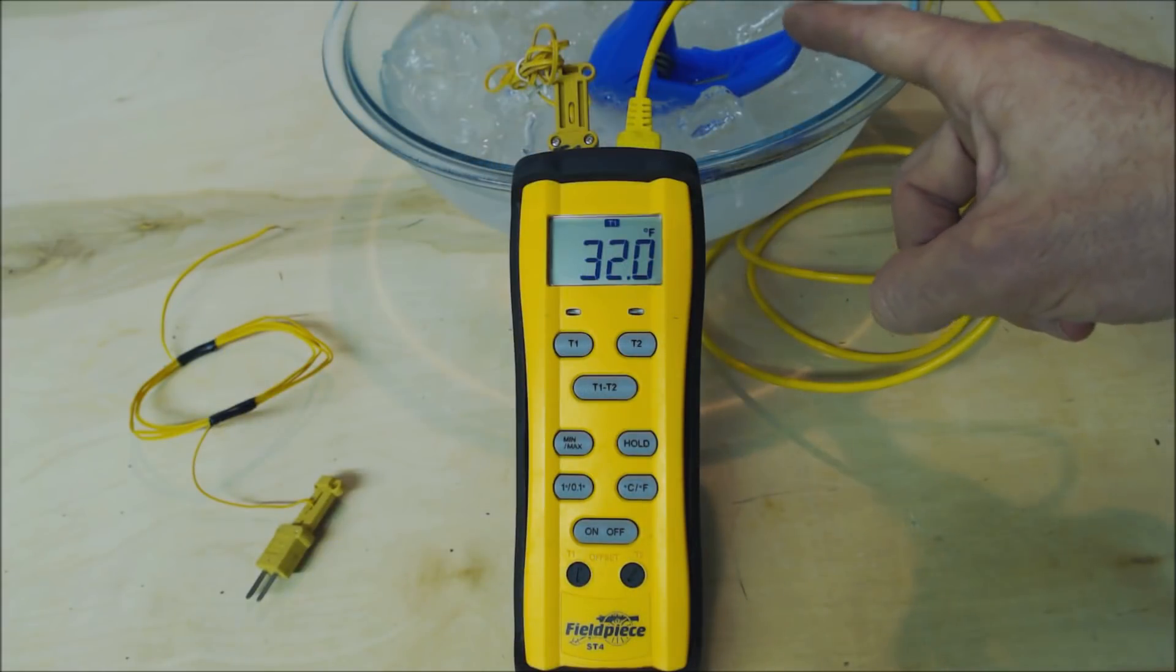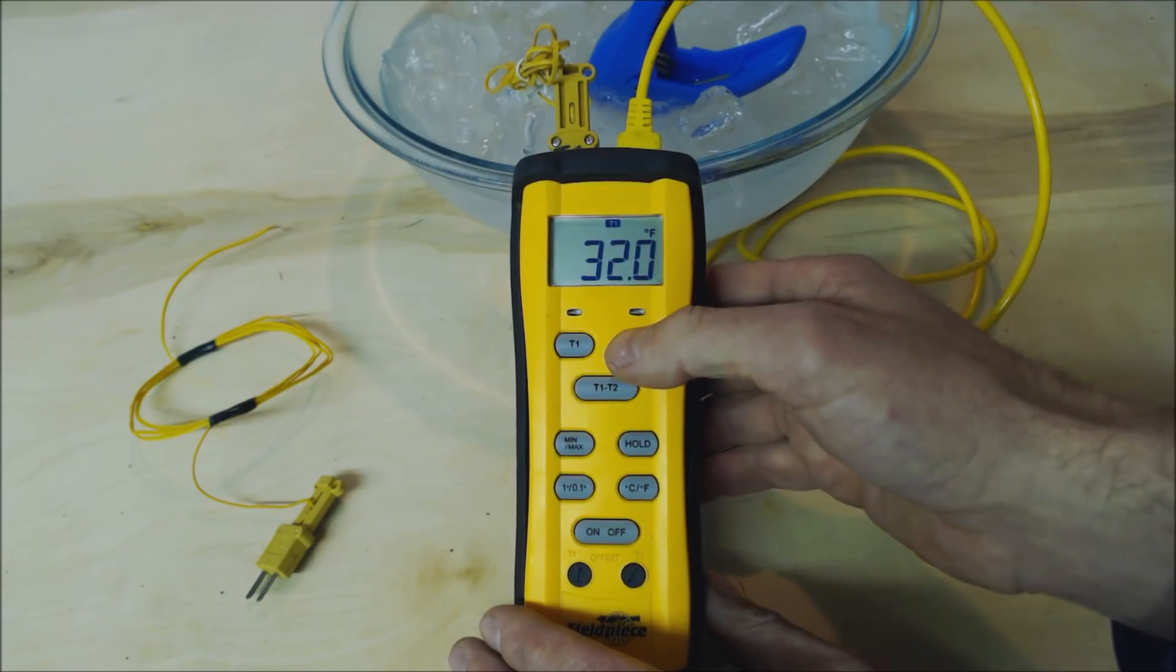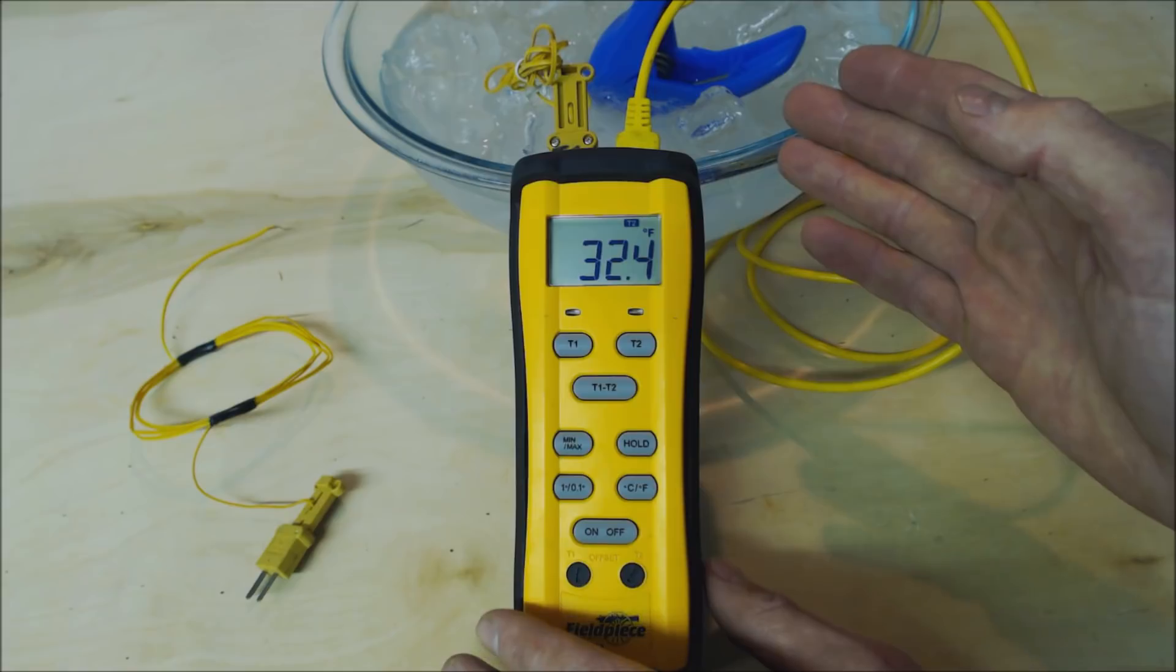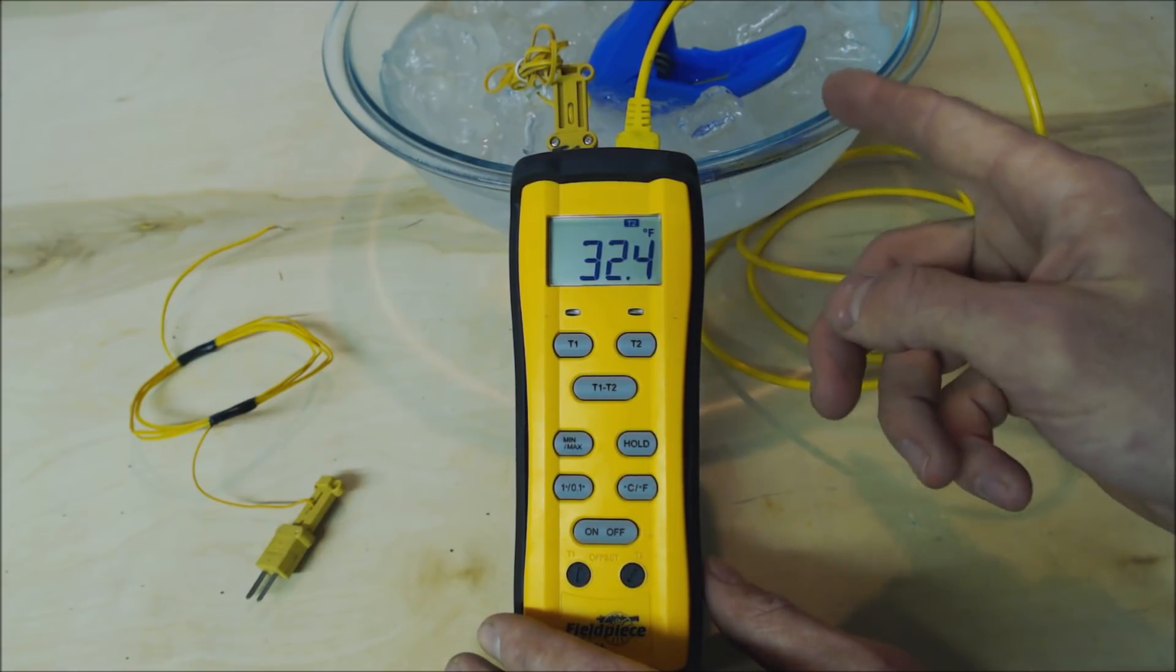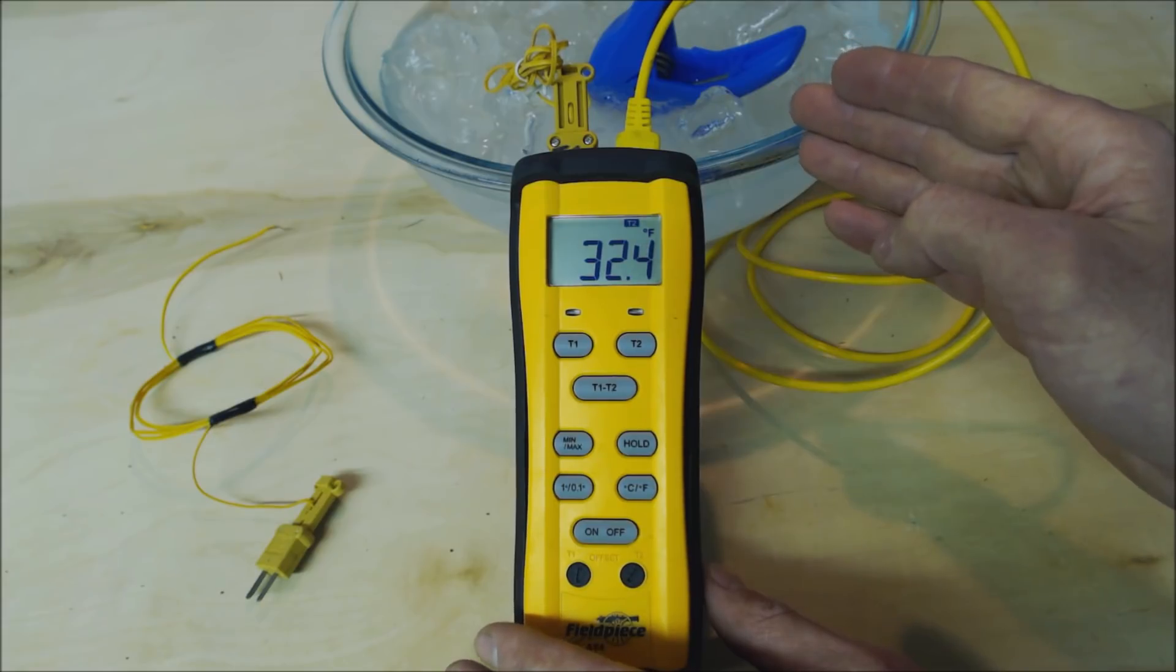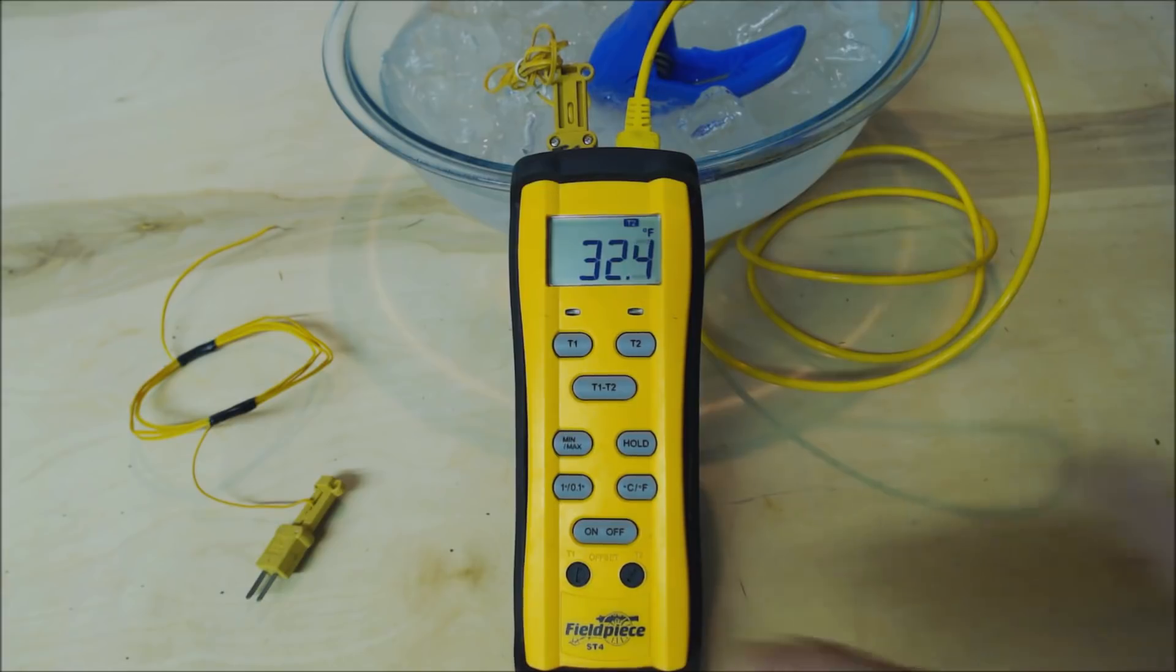This clamp has been sitting in this ice water for about five minutes. On T1 we're reading 32 degrees and let's go over to T2 and it's really not bad at all actually. 32.4. So it's only 0.4 degrees off. So that one happened to do very well. We would just need to adjust this counterclockwise to get it down to 32 and we'd be good to go.